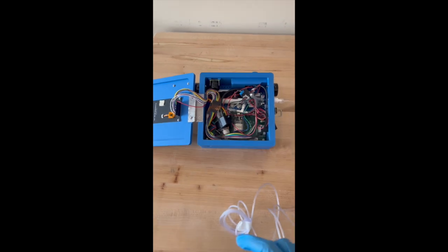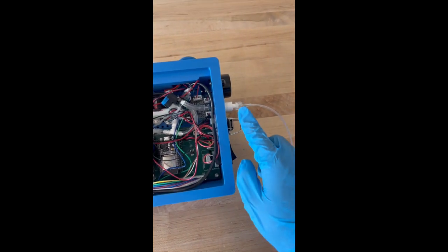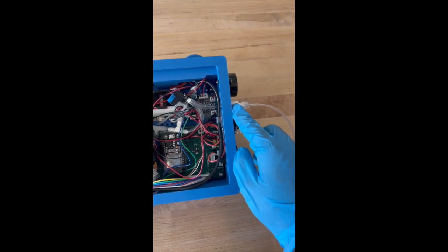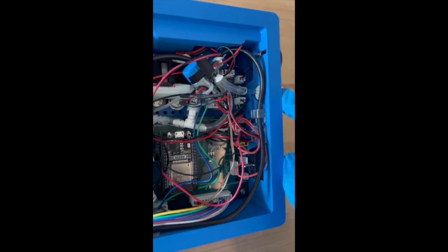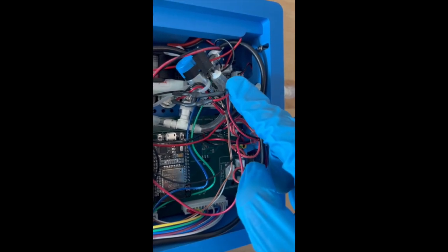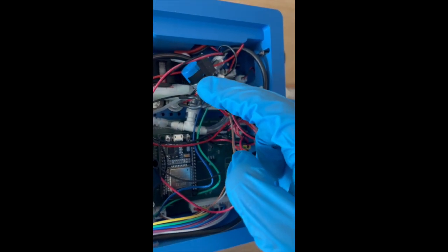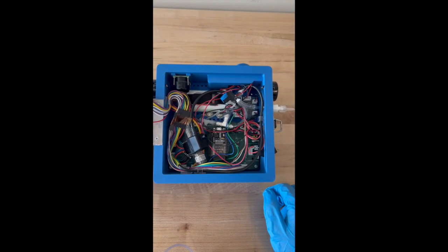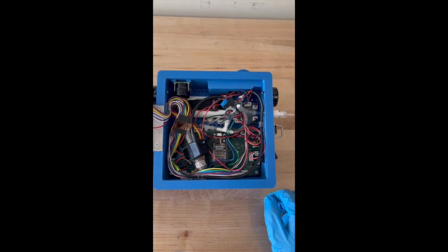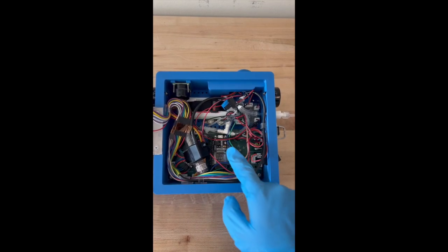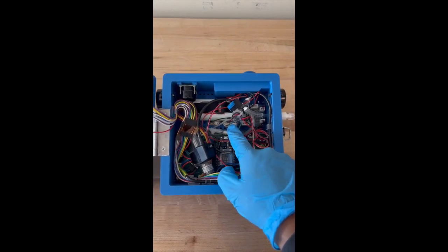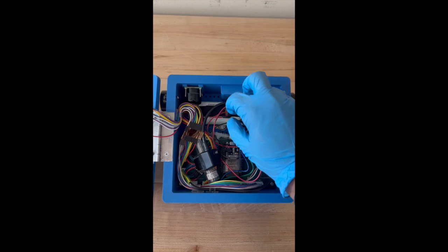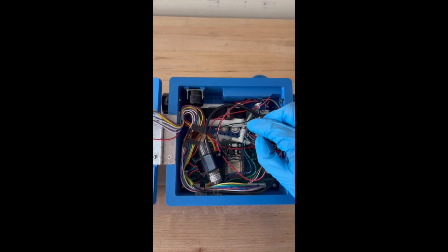It features the PCB, all the electronic connections, and the pneumatic workflow, which begins from the luer lock connector that goes to the filter that stops condensation from entering our line, and then air is sucked in through the diaphragm pump that we have, which then goes to the RH and temp sensor that enables us to tell if there's condensation in the line, as seen by that T over there. Behind the pump, which you can pull back to view.